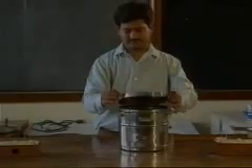Secondly, the packing should protect the material from contamination by bacteria from the environment after removal from the autoclave. Here you can see the material to be autoclaved being packed. Glass syringes, dressings, gloves, and rubber catheters are properly packed and wrapped in permeable wrapping, cloth, or kraft paper. A chemical indicator strip is also put on the packed material to check the satisfactory completion of the process.